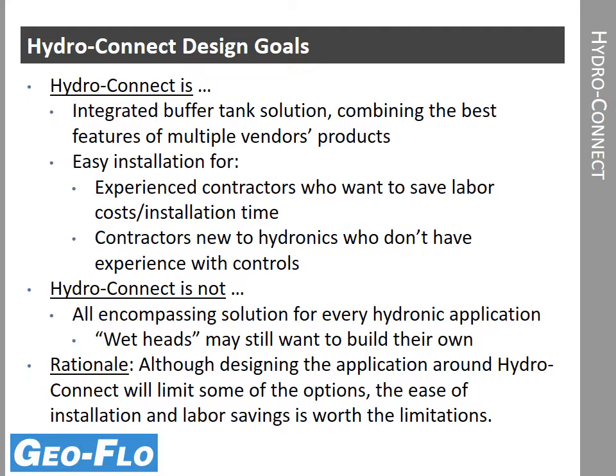Now, Hydroconnect is not really an all-encompassing solution, so it won't handle every conceivable application. The so-called wet heads, or the specialists in hydronics, will possibly find that Hydroconnect is somewhat limiting, and so it may not work for every application. But really the rationale is to find a system that can handle most of the options. We think about 80% or so, and installation time will be alleviated as a result, and so it will handle most of them, but it's certainly not an all-encompassing solution.